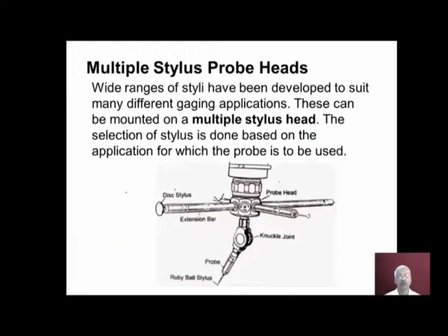Now, apart from single stylus probe heads, multiple stylus probe heads are also possible. You can see here we have a probe head with multiple stylus. This is a disc stylus with an extension bar, and this is a ruby ball stylus with the knuckle joint. Similarly, we can insert appropriate stylus here depending upon the inspection requirement. A wide range of styli have been developed to suit many different gauging applications. These can be mounted on multiple stylus heads. The selection of the stylus is done based on the application for which the probe is to be used.